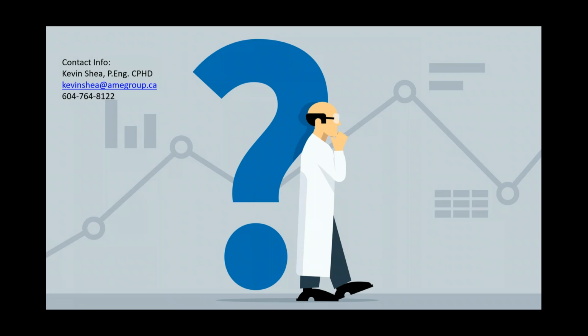We do have a question for you. In the case of a reduced airflow situation due to unoccupied system operation, how do you deal with the potential of chemical buildup due to improper bench practice or chemicals left at the bench or improperly stored in the laboratory? So that's where the Aircuity system really comes into play. It's going to continuously be monitoring those labs. And so those lower set points really just are the lower set points. But as Aircuity starts to sense anything in the labs building up, it's going to start increasing those airflows up to 8 air changes an hour.